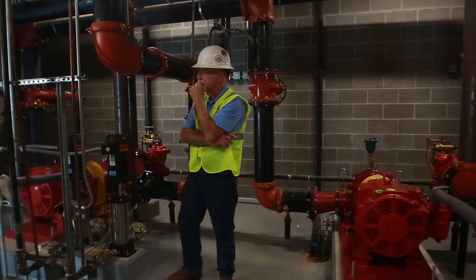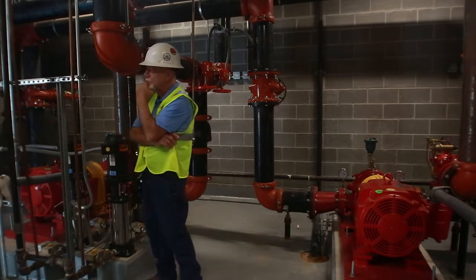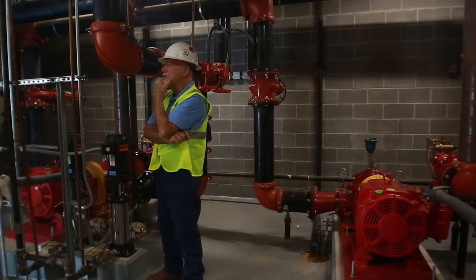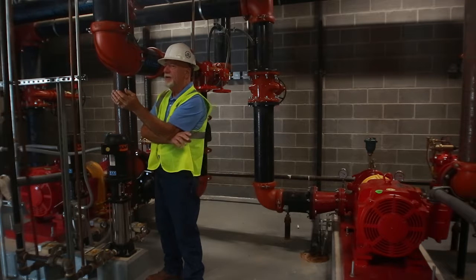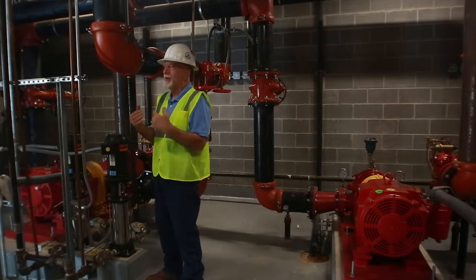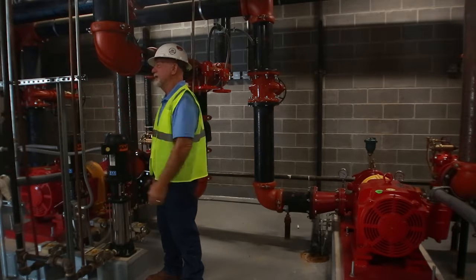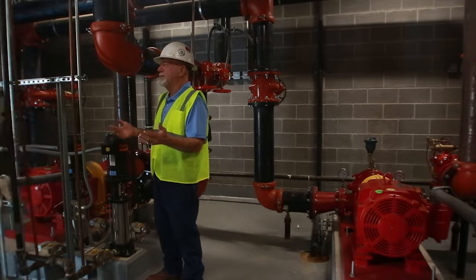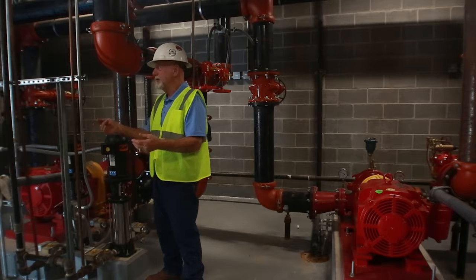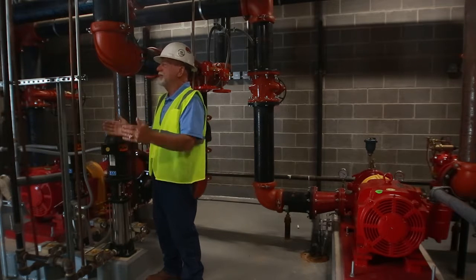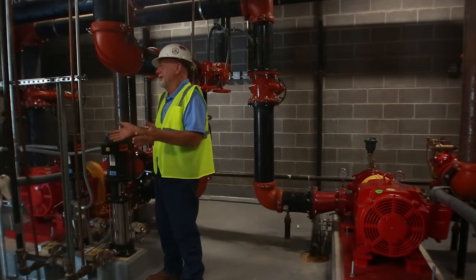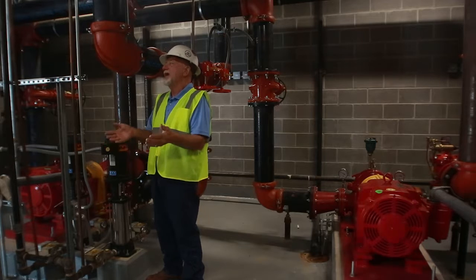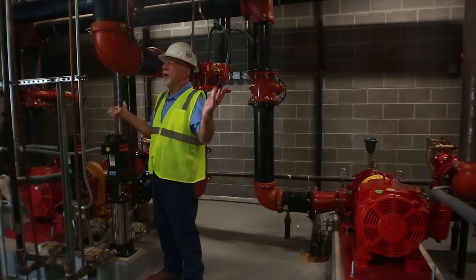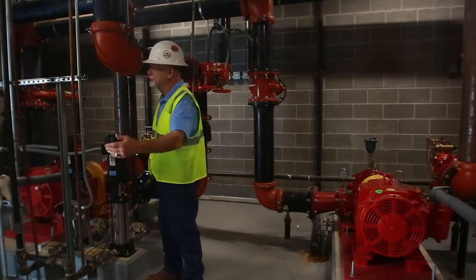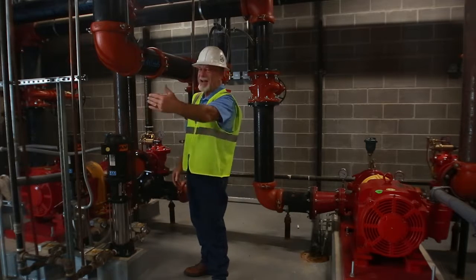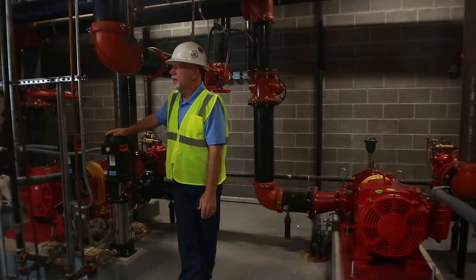So as long as pressure's normal, like we were talking earlier, we won't need to run a jockey pump to build that pressure up to then test the pump. Well, you shouldn't have to. Okay. But again, you have to learn, this is y'all's building. So I can sit here and tell you all kinds of good little things, but the truth is, you're the ones that got to deal with the consequences. If you walk in there, there's no point in creating a problem when you know the solution. All I got to do is push the button for a minute and I'm ready to go, and I don't create a problem. So in knowing that, the simple answer is probably that. If you have a fire and that pump comes on and it does something, well, okay, that's a different issue. I'm not going to start trouble that I can't finish. But either way, you do have options.